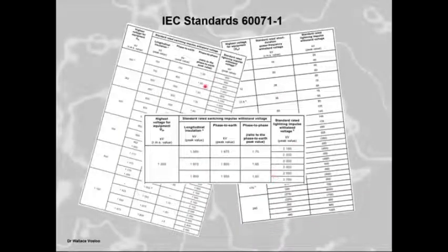Now, normally when you want to select your insulation, you find that up to a certain level, you will only take lightning impulses for short gaps. And then when you go to the longer gaps, you start taking in your switching, and this is all in the IEC standards 60071 part one. And this will help you to determine your lightning and your switching and your AC normal standard AC voltage levels.